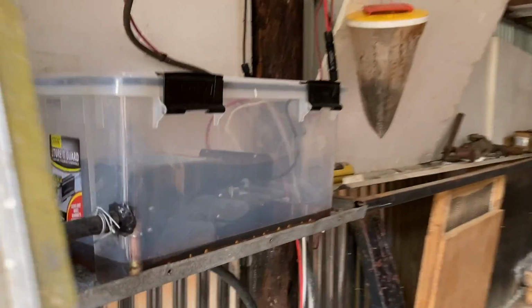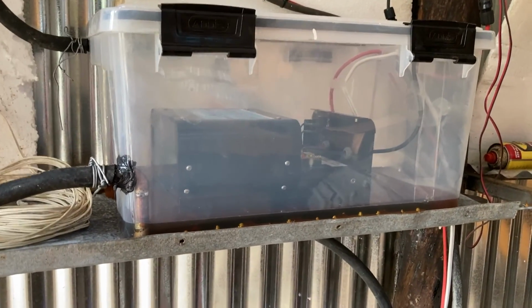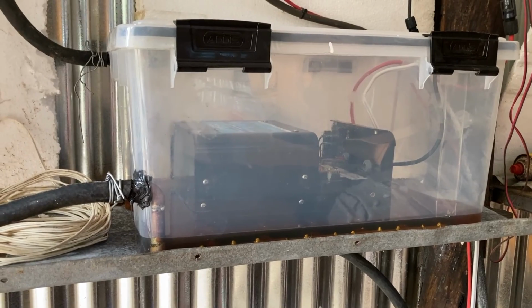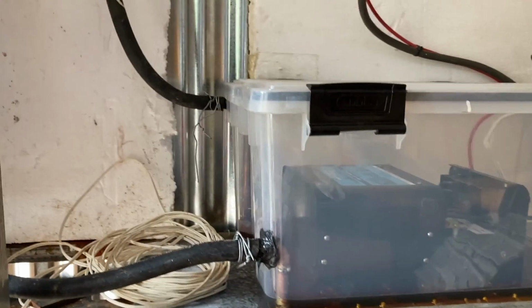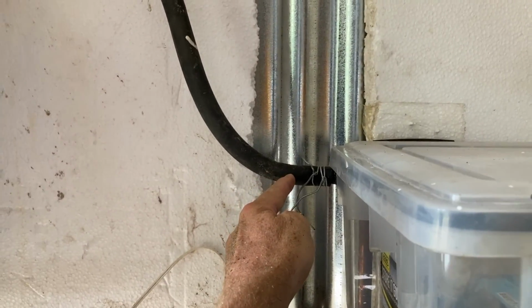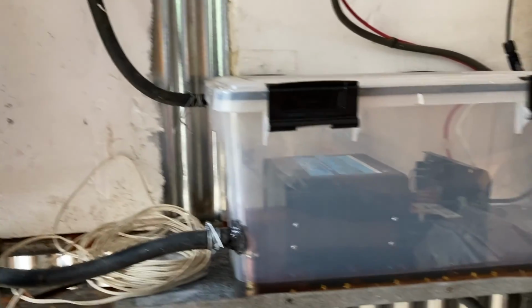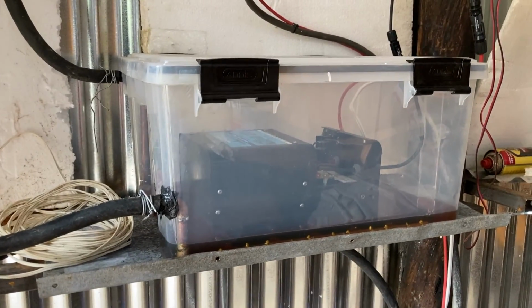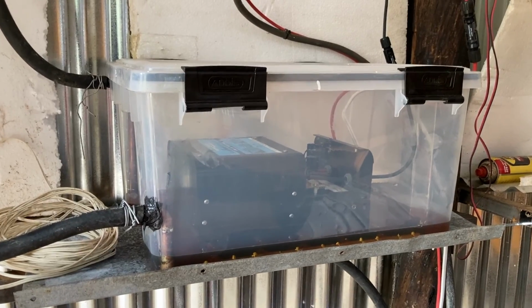Because if you have air inside the heat exchanger, it's not going to work. So you have to bleed the system, tip the heat exchanger so that the exit pipe, this one over here, is the highest point, and you'll hear the bubbles escaping, and then it should be good to do its thing. Okay, good luck with that.